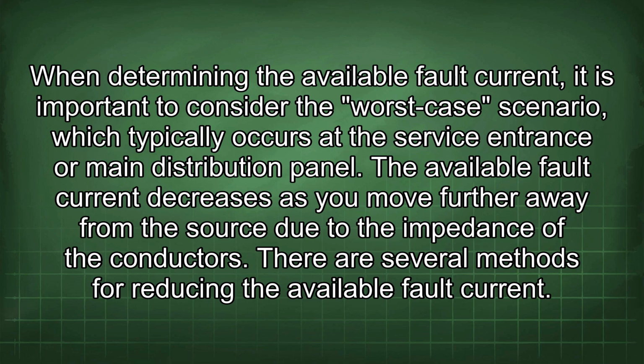When determining the available fault current, it is important to consider the worst-case scenario, which typically occurs at the service entrance or main distribution panel. The available fault current decreases as you move further away from the source due to the impedance of the conductors.